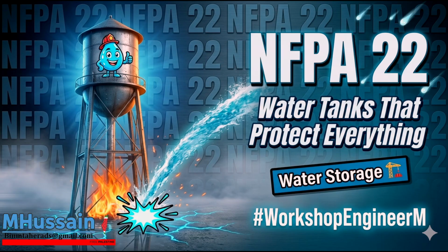Why exactly 15 feet? Modern fire trucks are incredible pieces of machinery. They have massive multi-stage centrifugal pumps capable of moving 1,500 to 2,000 gallons per minute, driven by 500 horsepower diesel engines. They're beasts. Why can't a pump with that much raw mechanical power pull water up from a tank buried 30 or 50 feet underground?